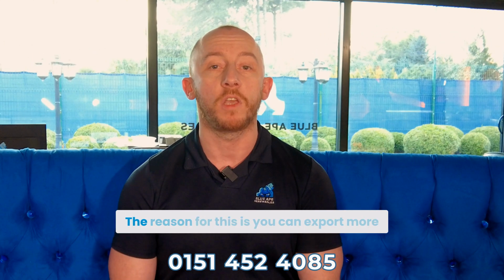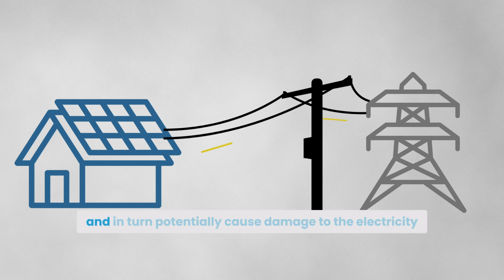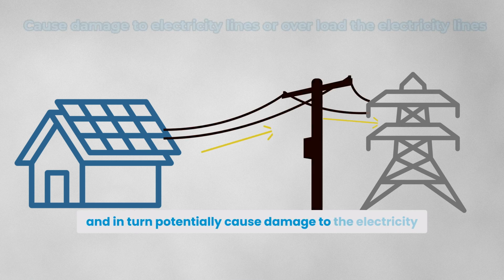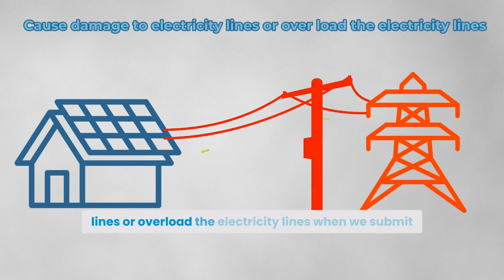A G99 application is required when we install an inverter, or combination of inverters, greater than 3.68 kilowatts. The reason is you can export more electricity back to the national grid, potentially causing damage or overloading the electricity lines.